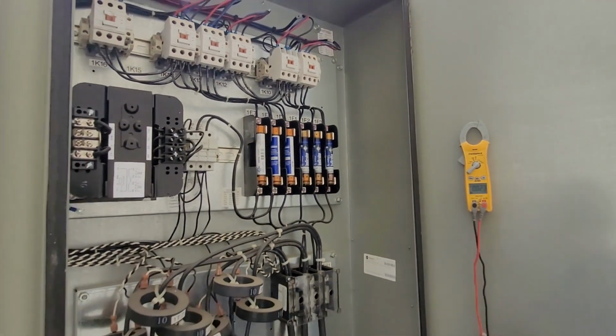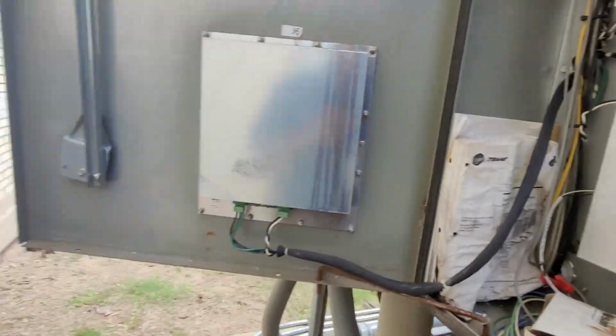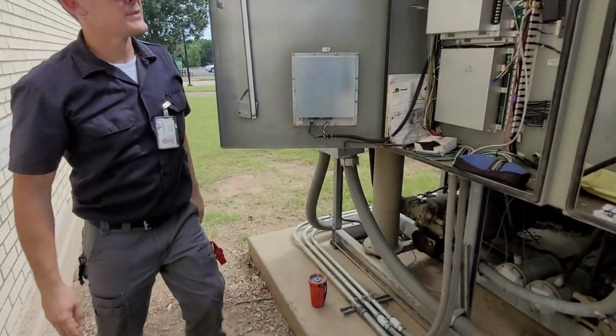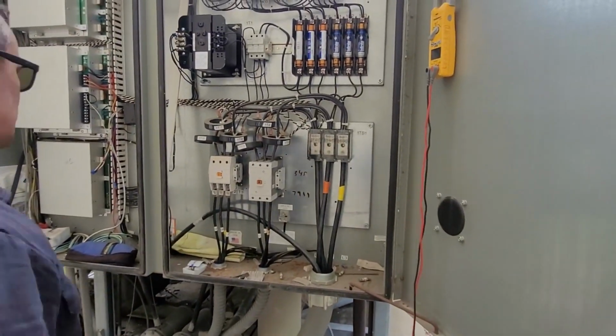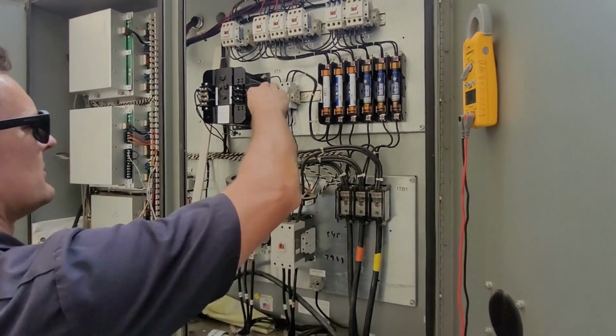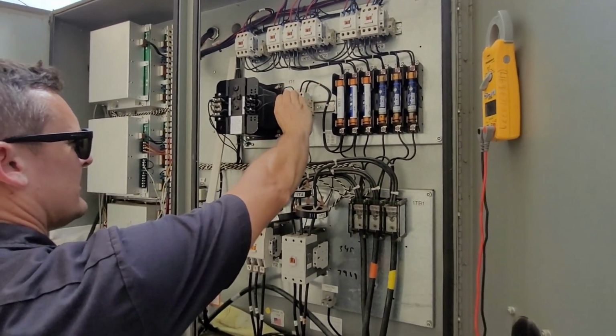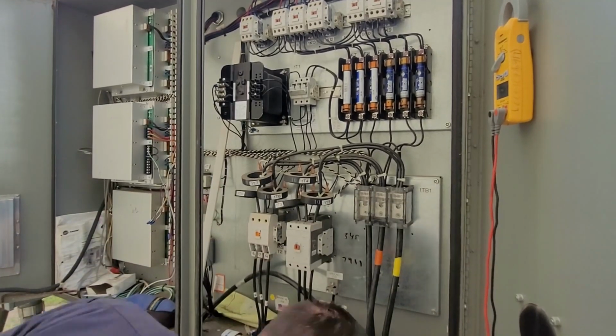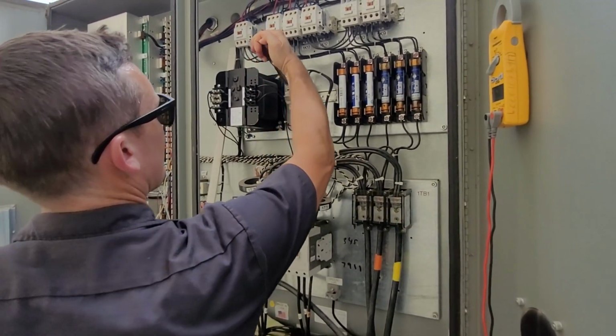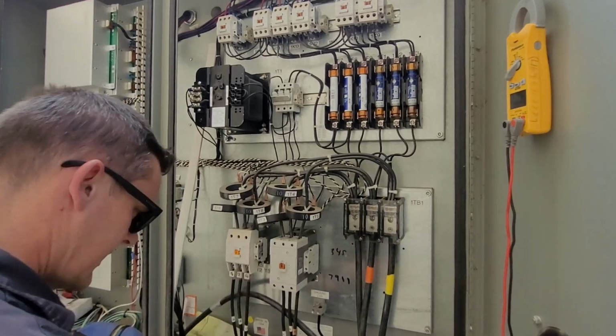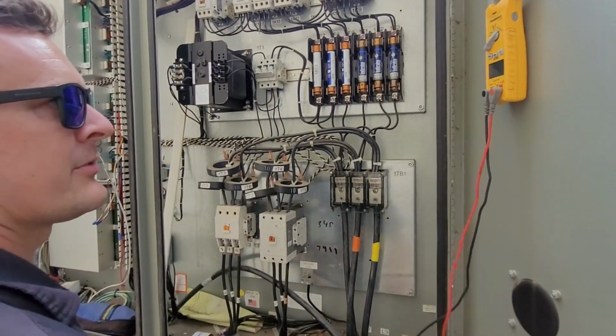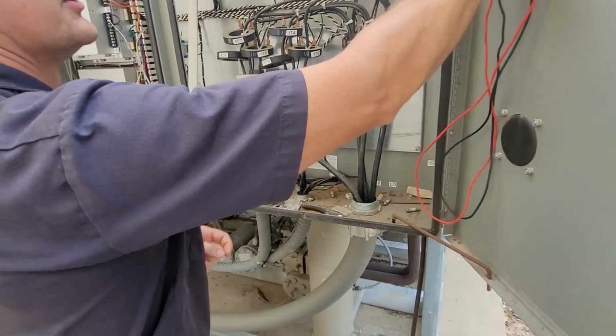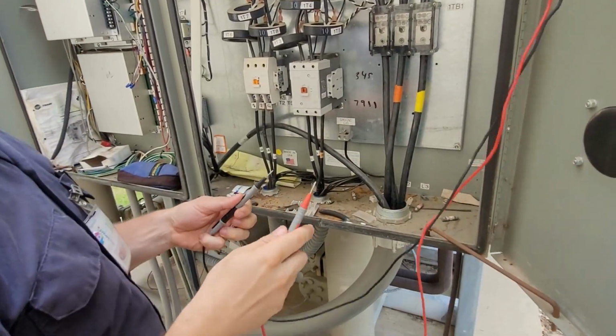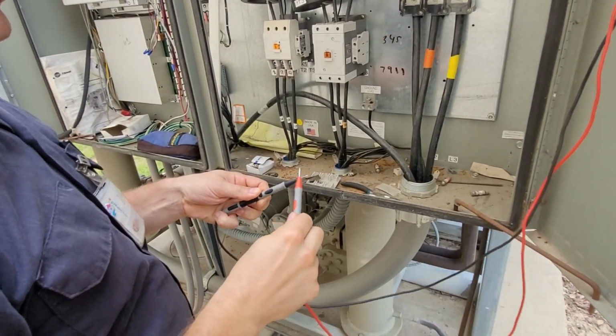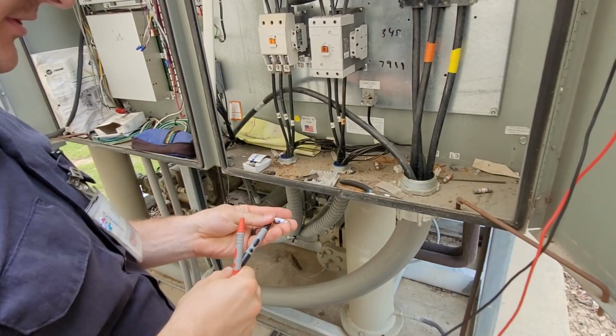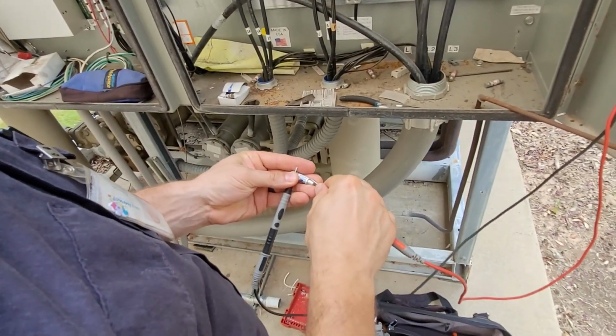So then the next step is to turn the power off. And it's always a good idea to wait a minute, but I know I'm safe. So I'm going to pull this fuse out. And then the next thing I do is I verify a third way, and that's continuity. So I set my meter to continuity. So it should beep if the fuse is good. No beep, so the fuse is bad.